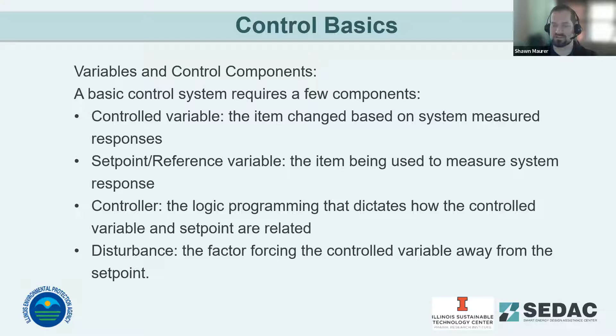What we see at a lot of plants currently is a reactive or feedback control strategy. You've got a DO sensor in a basin that's measuring DO, and in reaction to that, you adjust the speed of blowers, the positioning of valves, in order to maintain the set point of the DO system. It's a very common strategy. It's been effective for a while now, but what we're finding with more advanced technologies coming out is we can now move into a predictive or a feed-forward control system.